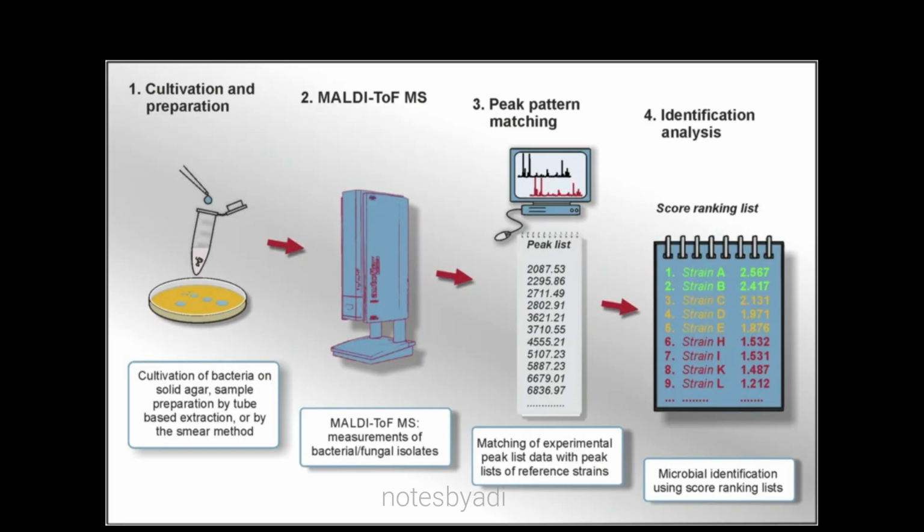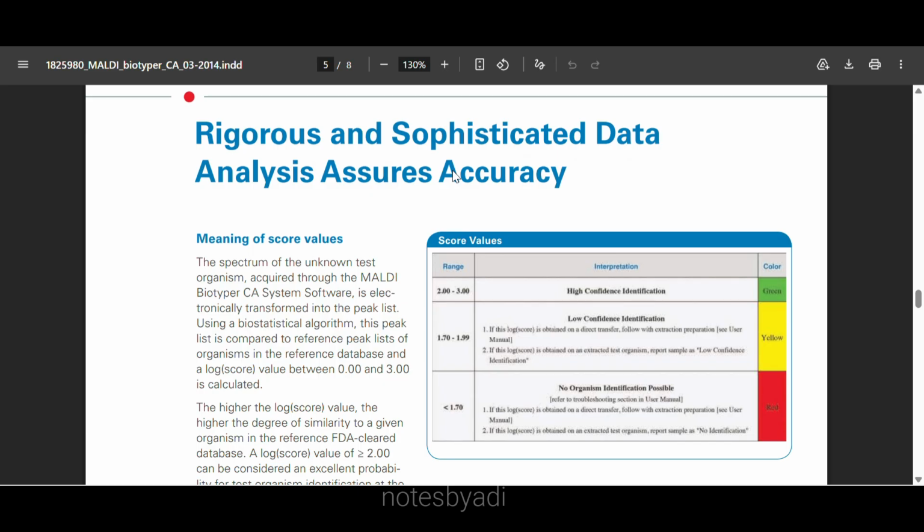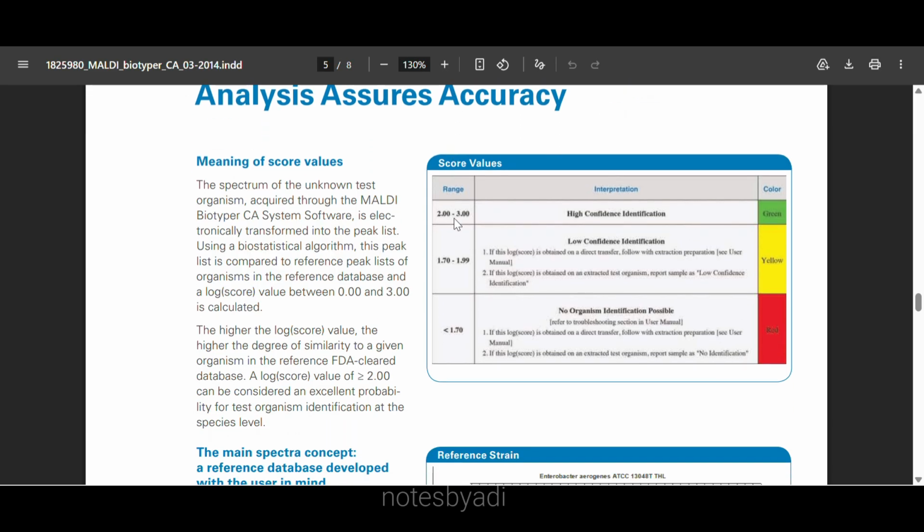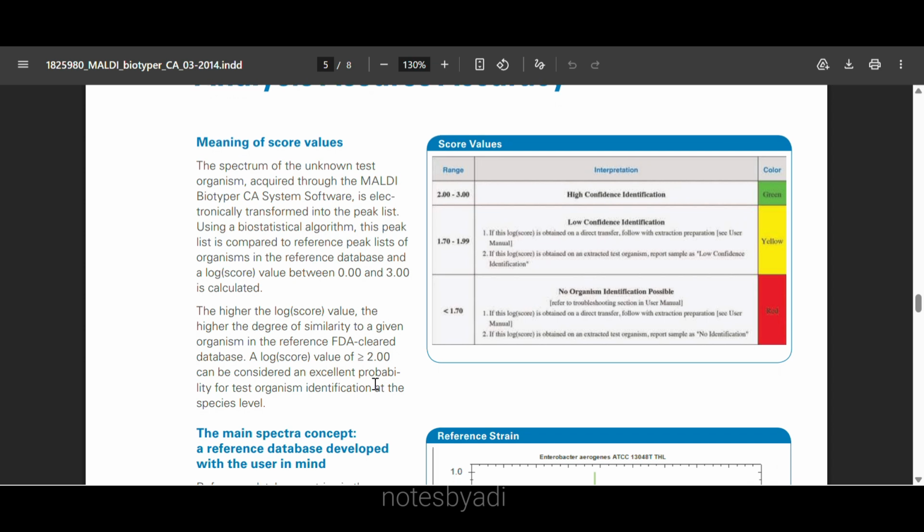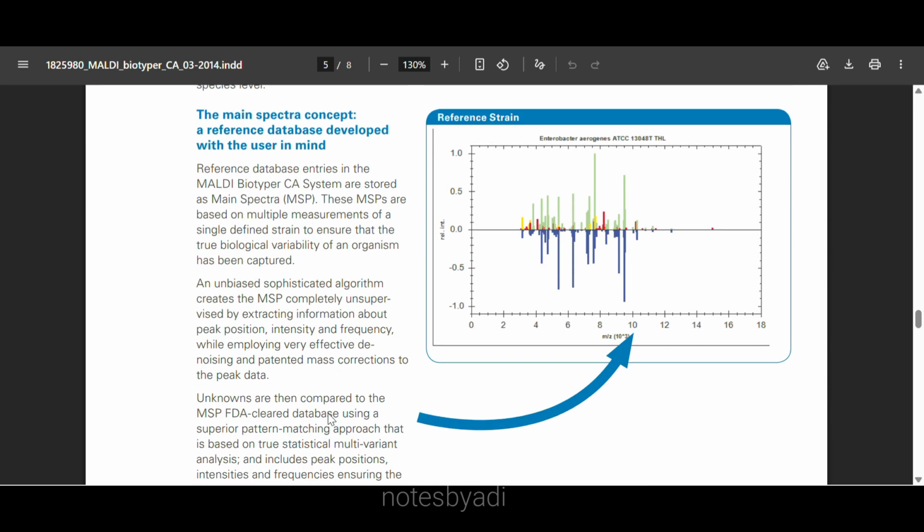This is so exact that using MALDI-TOF from a system like Bruker Biotyper, we can detect microorganisms with an identity score. This score has a known interpretation such that only a score of more than 2 is considered a confident species detection, while anything lower could be confident for genus level or even unreliable.